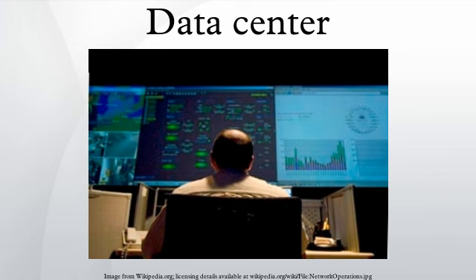Thermal zone mapping. Thermal zone mapping uses sensors and computer modeling to create a three-dimensional image of the hot and cool zones in a data center. This information can help to identify optimal positioning of data center equipment. For example, critical servers might be placed in a cool zone that is serviced by redundant AC units.